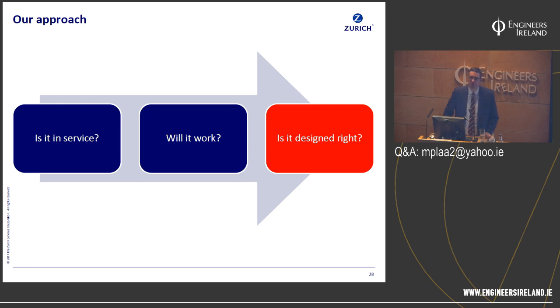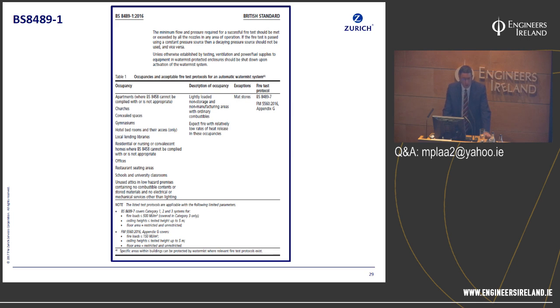How do we verify the system design? So I'll give you some tips and hints on how to do that when you come across these in the field. Now you can look at BS 8489 part 1. And when you're looking at design, bear in mind that at the moment within 8489, there are only a limited selection of occupancies where test protocols exist. So it's important when you come across a project in a commercial industrial environment that you cross-map the application in which the water mist system is intended or is fitted with the relevant British Standard document to say, for example, where is it listed, where is the test protocol, and 8489 part 1 is a good starting point.